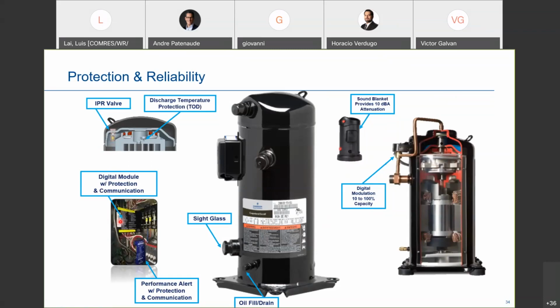If you're using digital, you have built-in CoreSense protection. The IDCM module has CoreSense-like protection. So if a customer wants to continue with that, that's great. You've got a digital, but the fixed capacity models don't. So you can add a panel CoreSense to that model. Just keep that in mind if you want total compressor protection from transcritical to subcritical. Panel CoreSense is definitely available for you to add on.